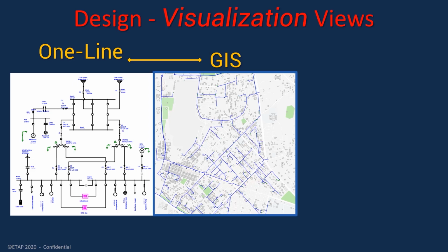On the center of the screen is the ETAP geospatial view of the grid imported from an existing ArcGIS database. The connectivity and all impedance information is automatically imported and brought in from the GIS database. On the left side of the screen is the OLV, or logical network view. This is commonly used by the protection engineer to look at the radial representation on main feeders, to set protection, create time characteristic curves, and also display other results such as incident energy or voltage drop, maximum available fault.